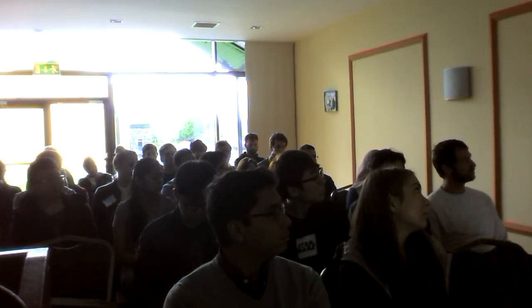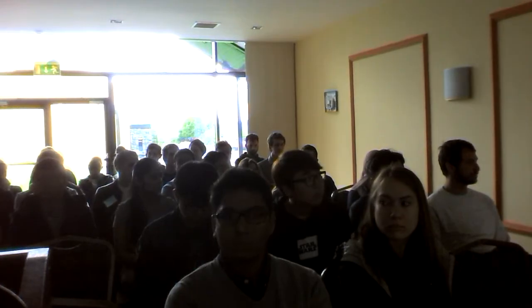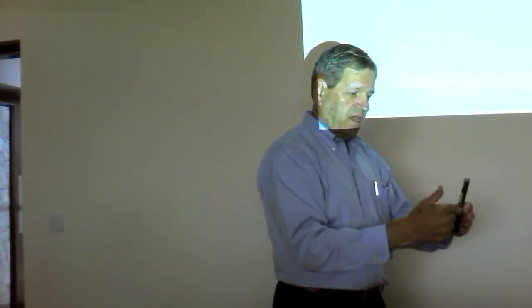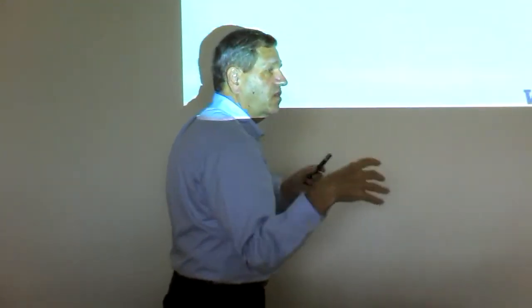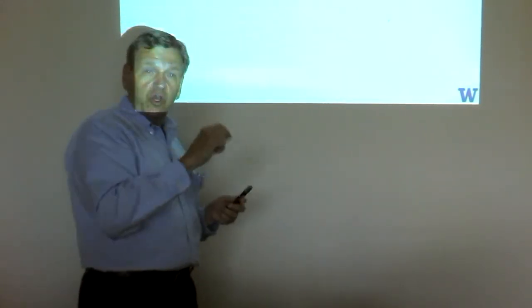Everybody get that? That was very, very well described. Could you give it to us again? Okay, so the idea is when you transmit focus, your intensity is going to be the highest at the focus. If you're either in front of or behind the focus, the acoustic field, which is illuminating the scatterers, is lower. But your receiver is exactly in focus. So in terms of spatial resolution, you're pretty darn close, whether you're in the transmit focus or away from it, because your receiver is dominating that. But your signal size goes down because you don't have as efficient a scattering event, which your receiver is viewing. And so you have a distribution, and it's asymmetric about the focus.